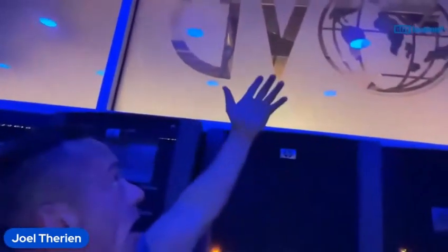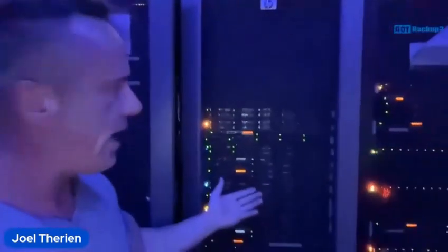4. And guys, it's 108 degrees today here in Texas. It's a cool 68 degrees in this room. And we keep the cooling efficient. So over here, where our logo is up there, that separates the cold aisle from the hot aisle. If you look above me, those vents are strategically placed right above the servers. So all the cold air comes right down, right in front of the servers, gets sucked in, okay?